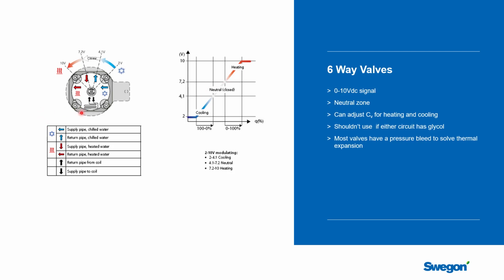Another thing about these valves is they typically have adjustable CVs, because you're going to have a different CV in heating and cooling, and so you may need to adjust that to get good valve authority. We mentioned the part about don't mix them with glycol. And you usually need to have some way of relieving the pressure. If you have a six-way valve that's servicing, let's imagine a classroom, which would typically have 4 to 6 chilled beams in the ceiling, there's a reasonable amount of water in the piping and in the coils.